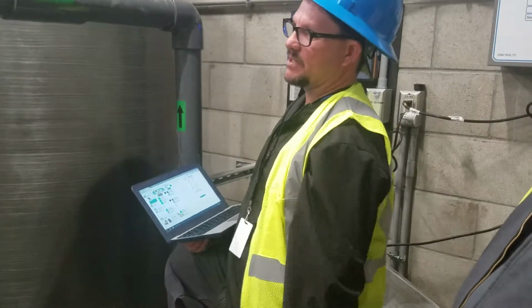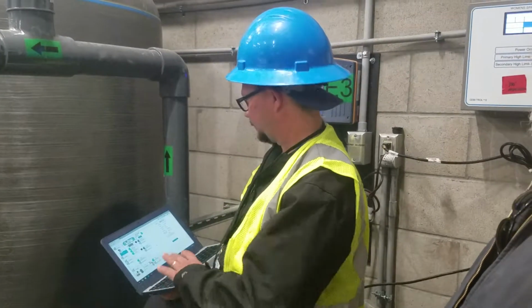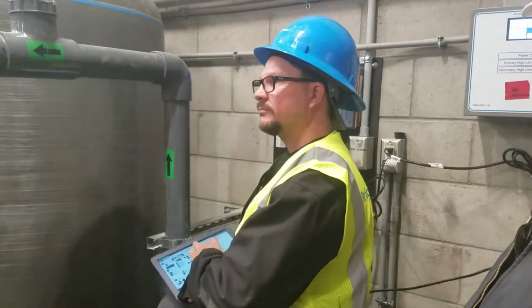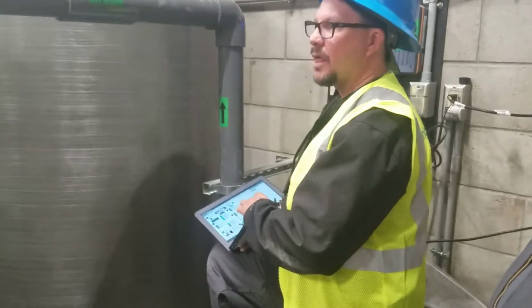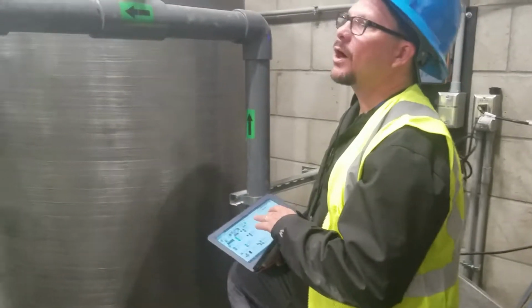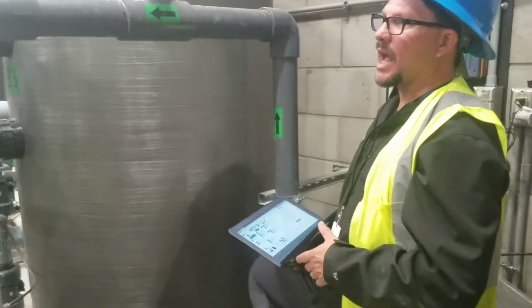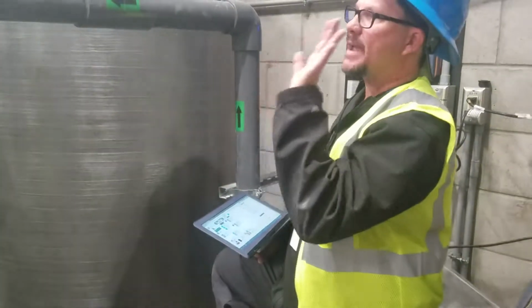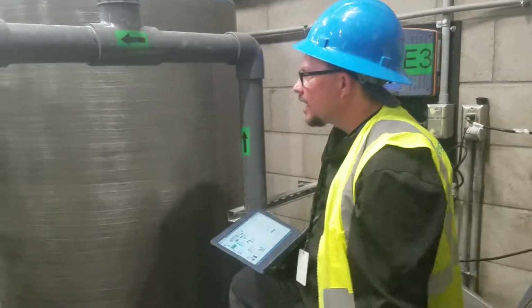Right, like for example, you're saying that although this seems to be overfeeding CO2 and bringing the pH too low, once we have a bather load and you start getting the chlorine feeding and raising the pH, then that might balance itself out. It may. We may not have that issue when we do have a bather load. Actually, it's too premature for us to start making drastic changes to mechanical anything. So you set it up in safe parameters to start off operating.